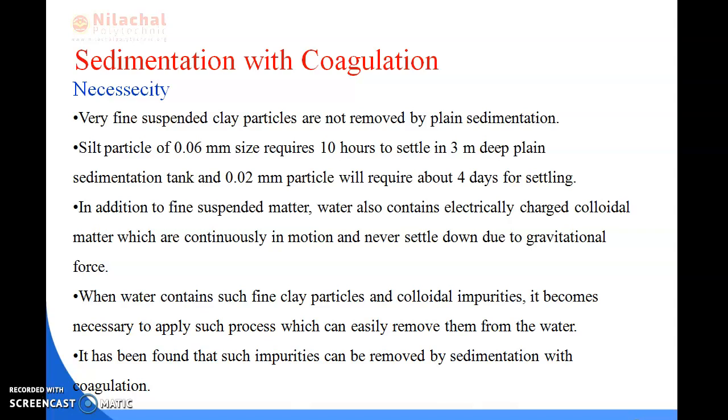A silt particle of 0.06 mm size requires 10 hours to settle in a 3 meter deep plain sedimentation tank, and a 0.02 mm particle will require about 4 days for settling. So we can say that a silt particle of 0.06 mm size requires 10 hours to settle in the sedimentation tank, but a 0.02 mm particle will require about 4 days for settling at the bottom of the tank.